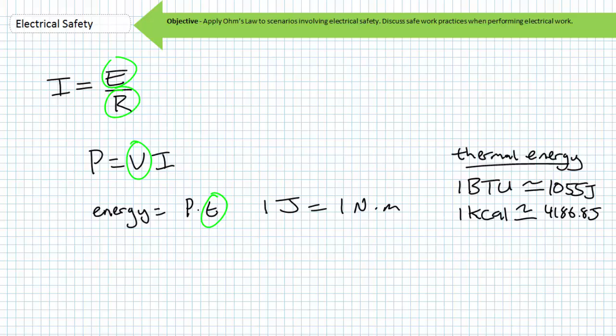Here's some general safe work practices you should follow when working with electricity. Never work alone. If your team is working remotely, stay in contact with your operations and maintenance organization. Turn the power off if at all possible. Certain measurements must be made with the power on, but if at all possible, turn it off when connecting instrumentation, then turn it back on to make the measurement. Never modify a circuit with the power running. You could accidentally short circuit critical current controlling elements.